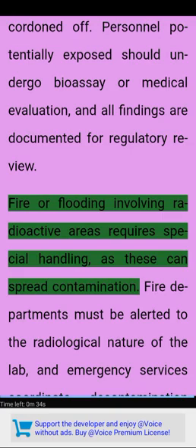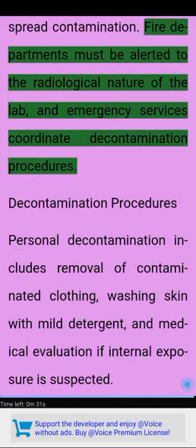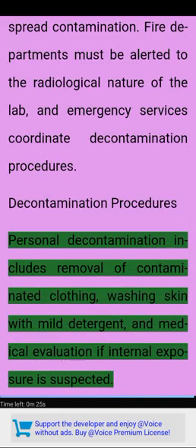Fire or flooding involving radioactive areas requires special handling, as these can spread contamination. Fire departments must be alerted to the radiological nature of the lab, and emergency services coordinate decontamination procedures. Decontamination procedures. Personal decontamination includes removal of contaminated clothing, washing skin with mild detergent, and medical evaluation if internal exposure is suspected.